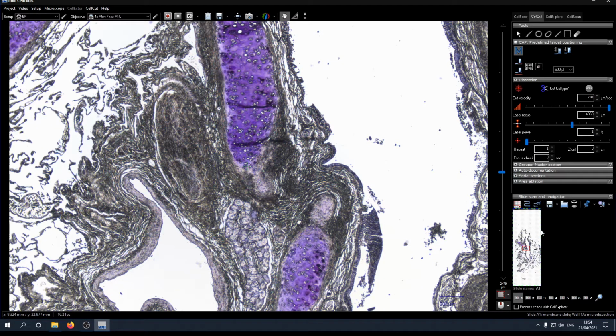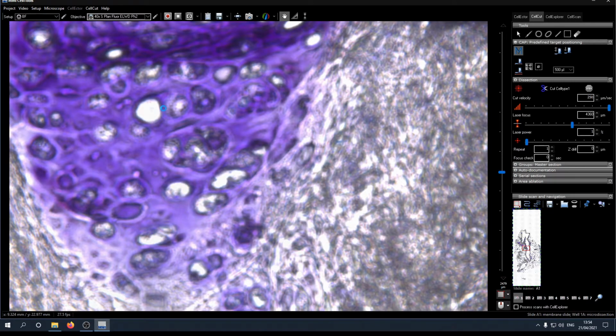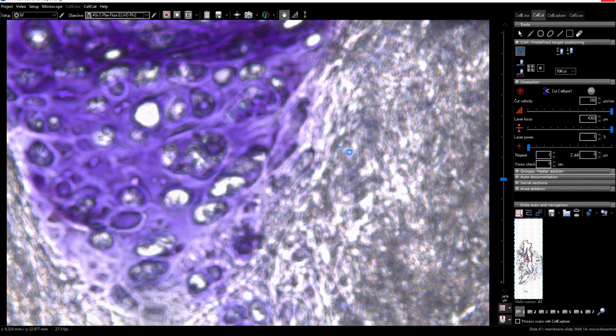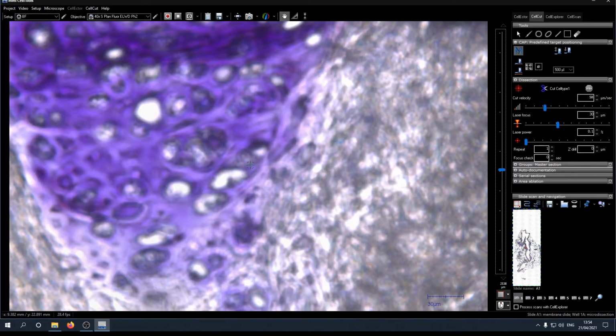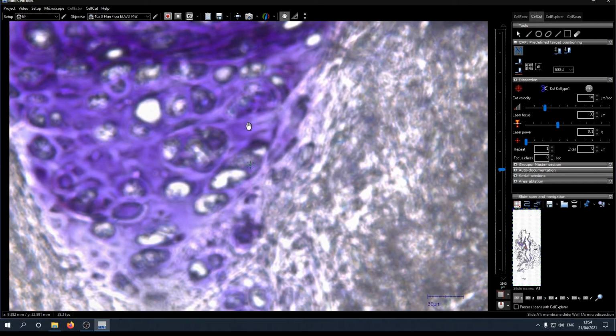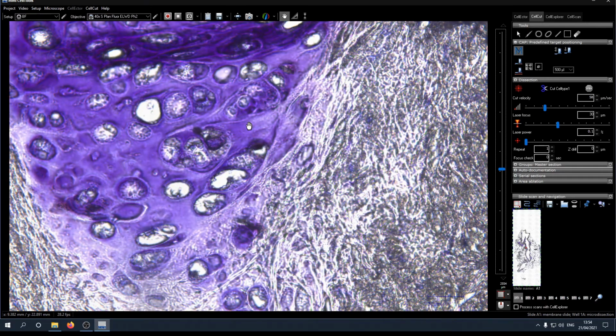Next, we have to set the parfocal lens offset. Therefore, we go to the highest magnification and get into the focus plane again. This can be done either with the slider or with your mouse wheel. After we found the focus plane, we click Setup and Parfocal Lens Offset.